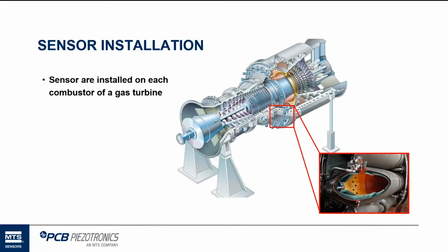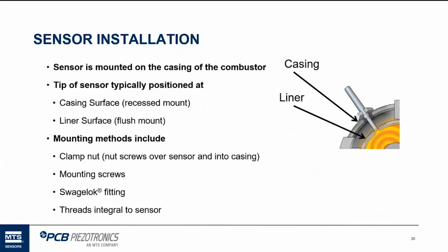combustion dynamics in line. You can see in the picture where the sensor's mounted, that square on the top is kind of showing a combustor. The lower picture on the right is where the sensor is mounted, where you see the red circle. It's a little hard to see these, I understand that. Apologies, but that's kind of the best we got. So yeah, the sensor's mounted so that the tip is just inside the liner. So where all the combustion is going on is where the tip of the sensor is mounted, just outside of that, as you can see in that picture.